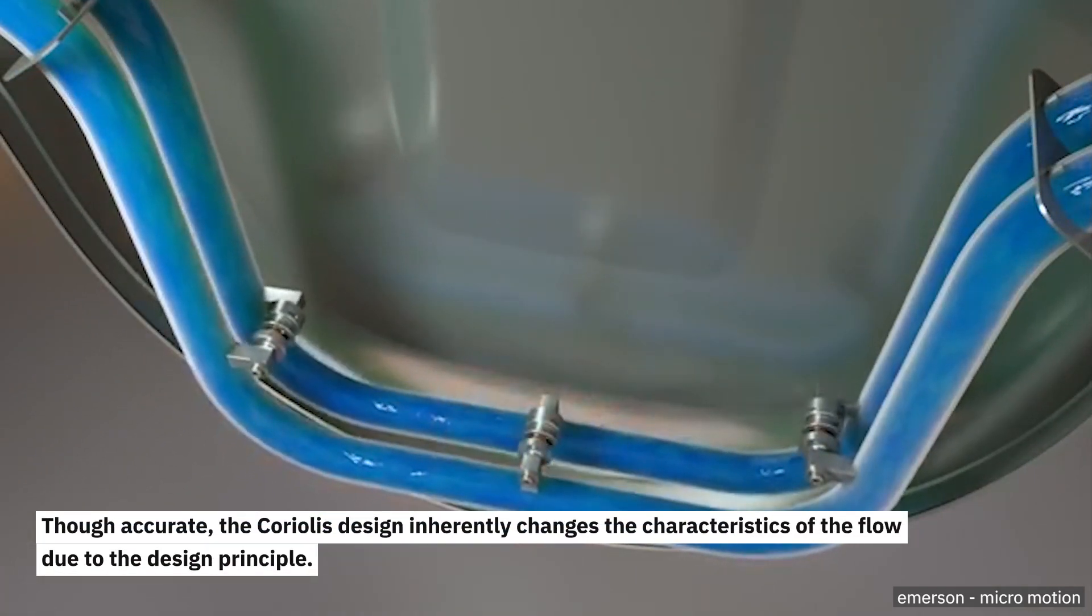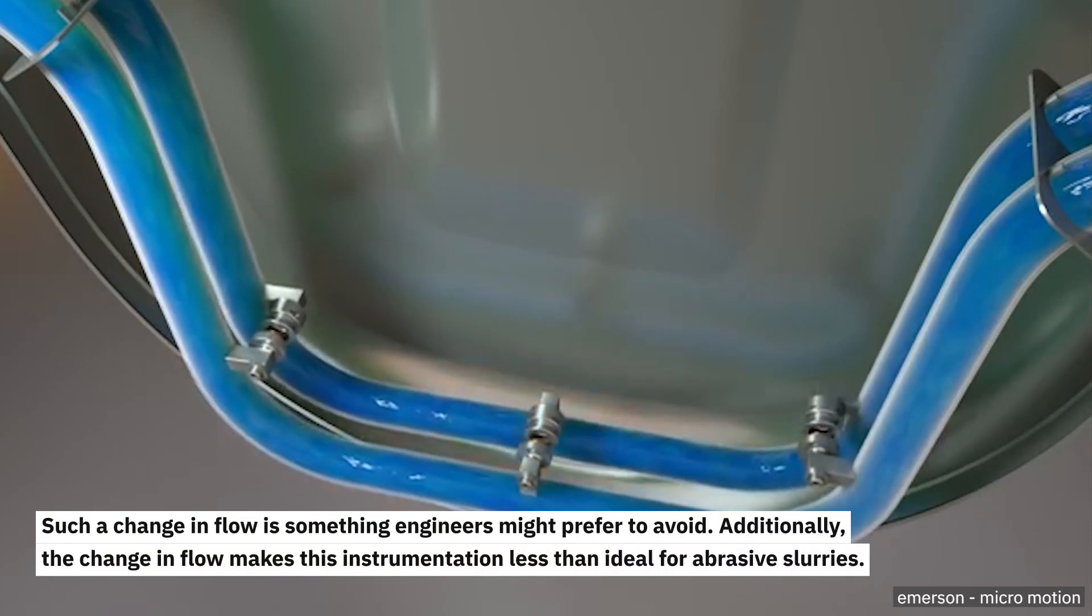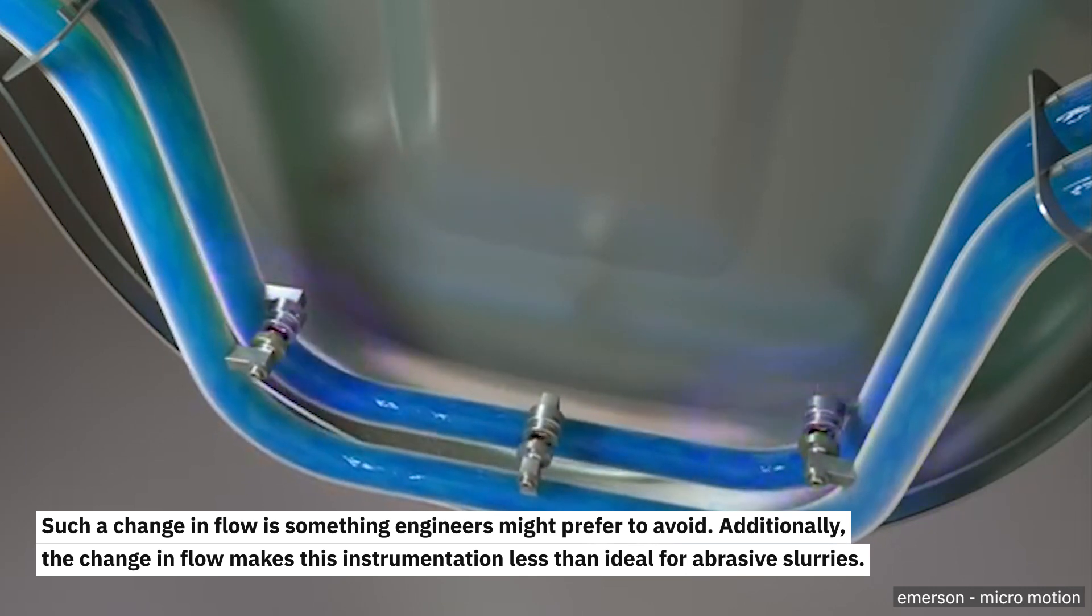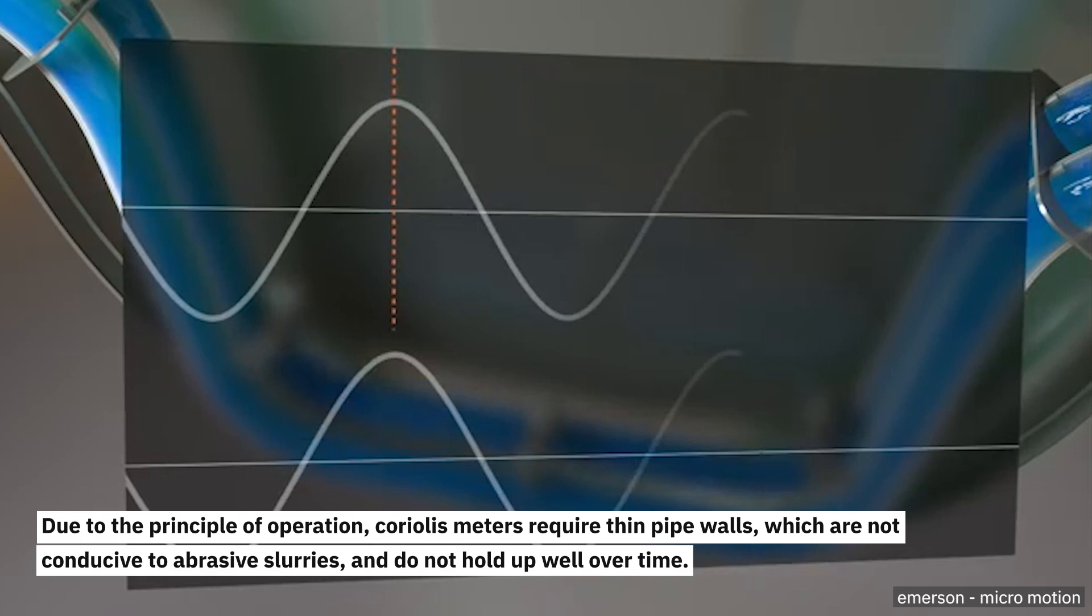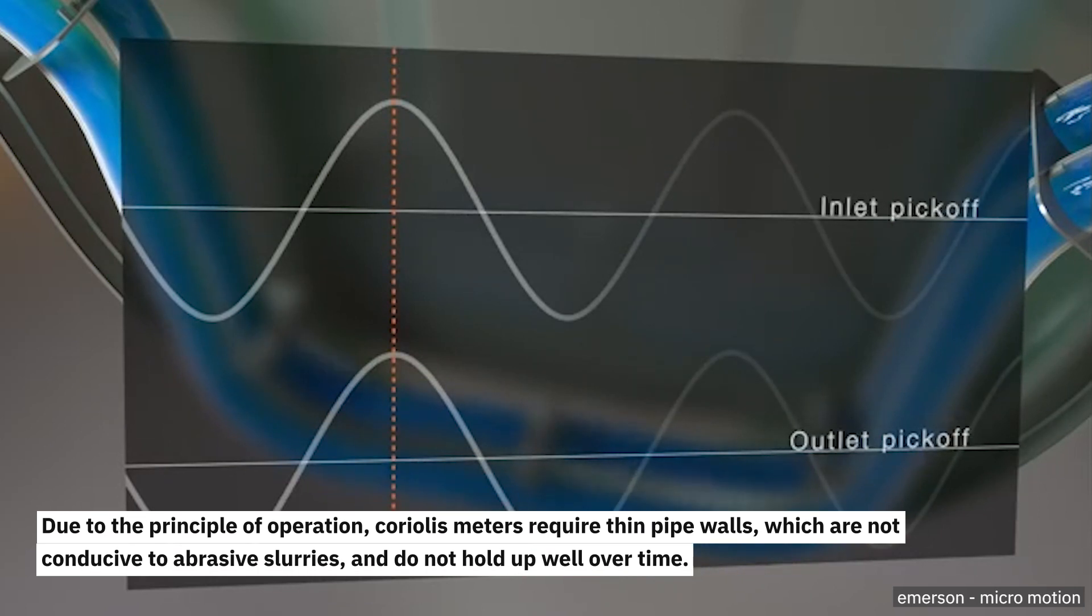Such a change in flow is something engineers might prefer to avoid. Additionally, the change in flow makes the instrumentation less than ideal for abrasive slurries. Due to the principle of operation, Coriolis meters require thin pipe walls, which are not conducive to abrasive slurries and do not hold up well over time.